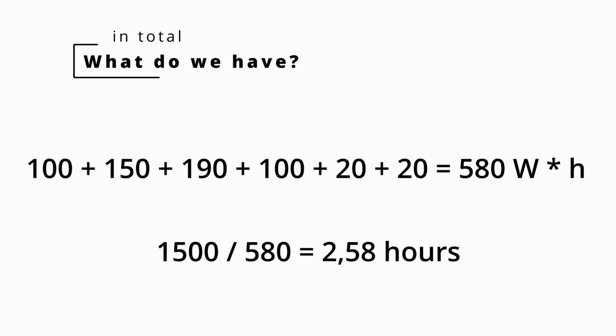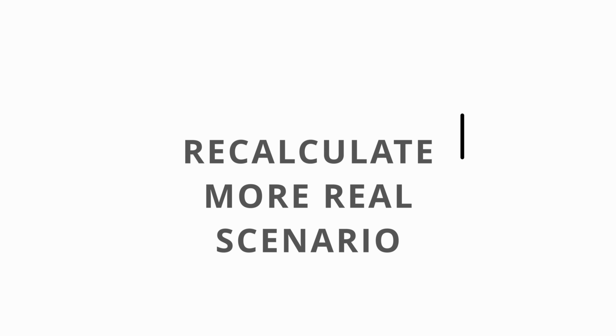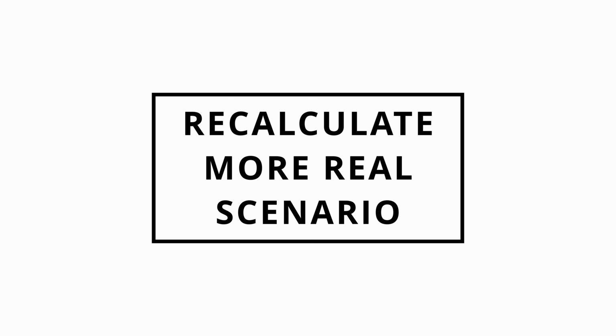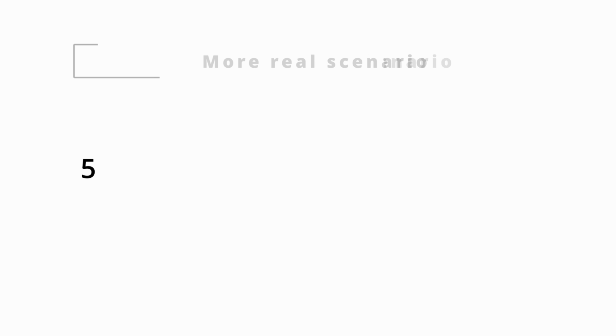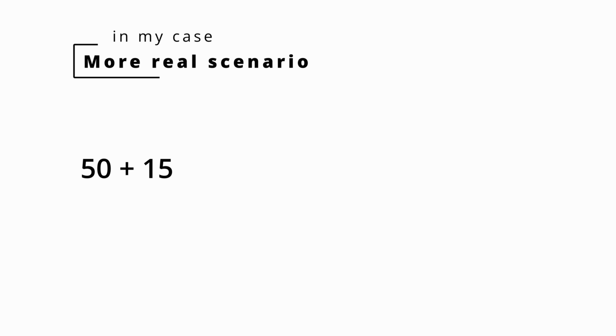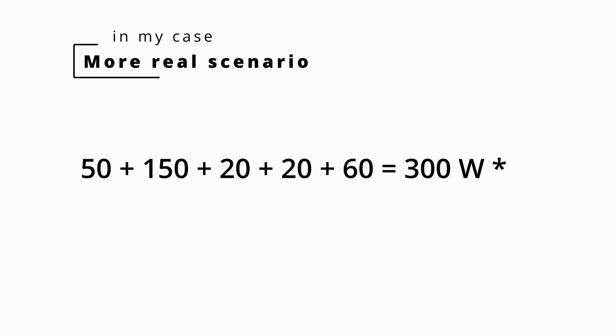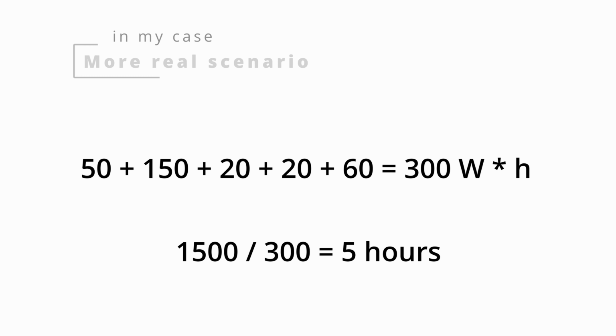But I almost never use appliances from the backup power supply, and the refrigerator does not always work. Therefore, if we translate this to a more realistic scenario, we have a refrigerator consuming 50 watts. Let's assume it operates 50% of the time, and a pump consuming 150 watts per hour. Routers consume 20 watts, and without the television and lighting in 2 rooms, which is 60 watts. In total, we have 300 watt-hours of consumption, and our 1.5 kWh is enough for 5 hours already.